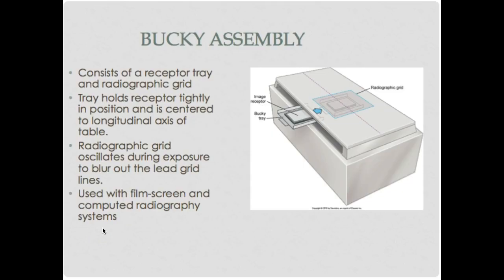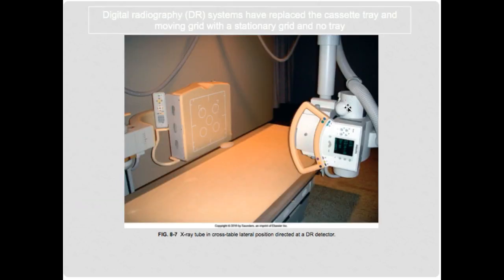The Bucky assembly consists of a receptor tray and a radiographic grid. You put your image receptor in the Bucky tray and there's a grid set inside the table. The grid oscillates during the exposure to blur out any lead lines within the grid. We use this with film screen and computed radiography. With a DR system, the cassettes and cassette trays are taken out and it's a direct digital device — typically 17 by 17 — and there are two different ways it captures: direct and indirect.